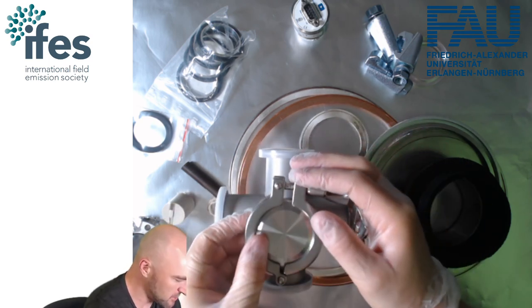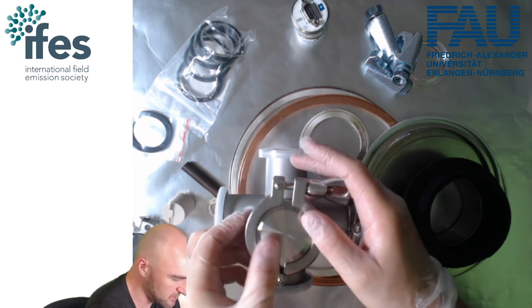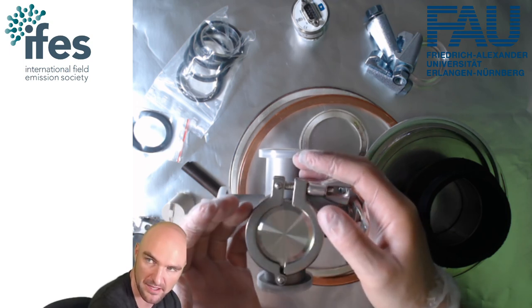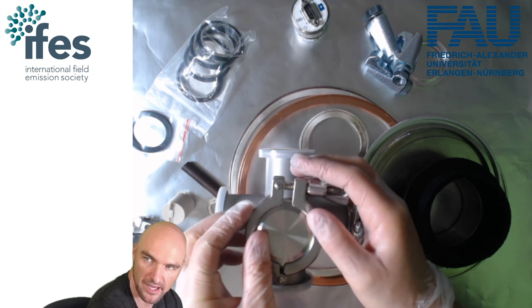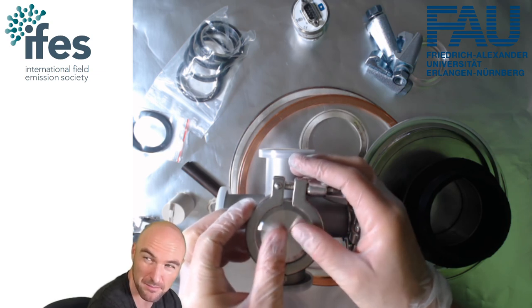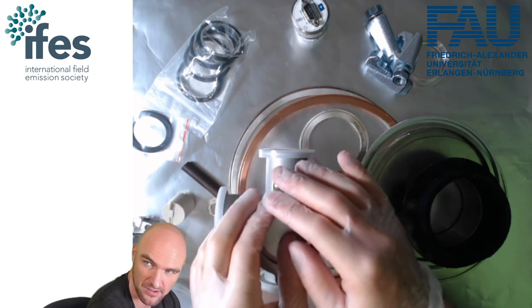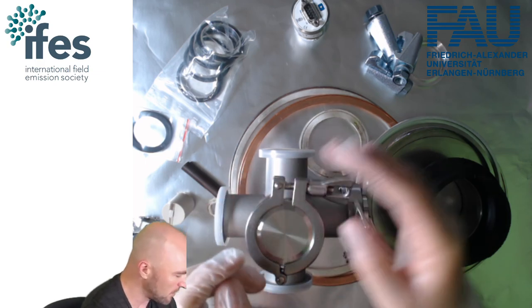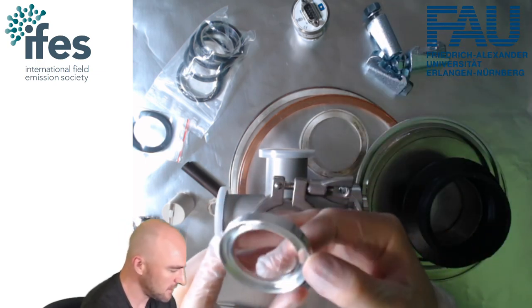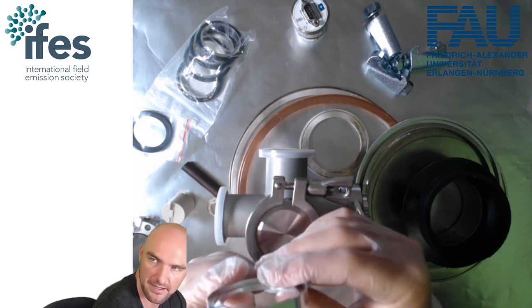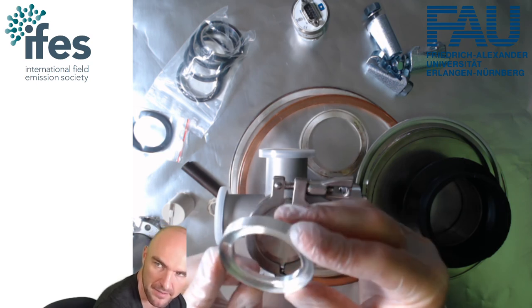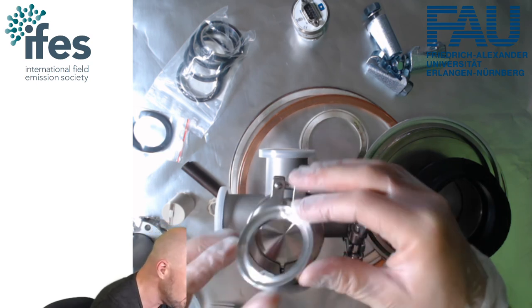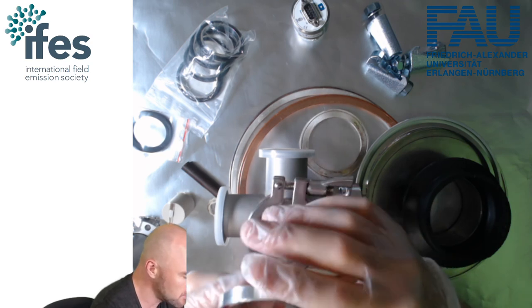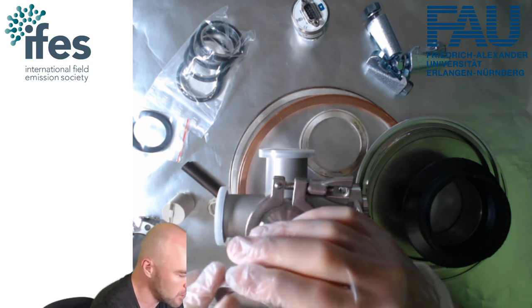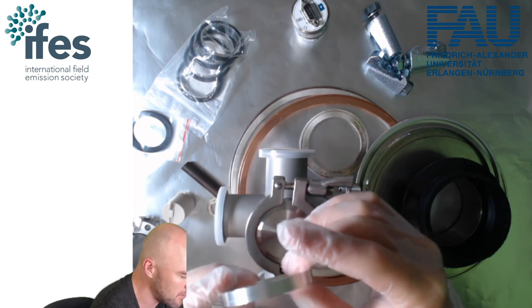And this is pretty much everything there is to these flanges. These flanges are a lot cheaper than CF flanges, and they can get you down to roughly 10 to the minus 7, 10 to the minus 8 millibar with rubber gaskets. But if you want to go lower, you can buy metal gaskets. So this is an aluminium gasket that would fit into here. And if you use those aluminium gaskets, you can actually go into the 10 to the minus 9 millibar range.